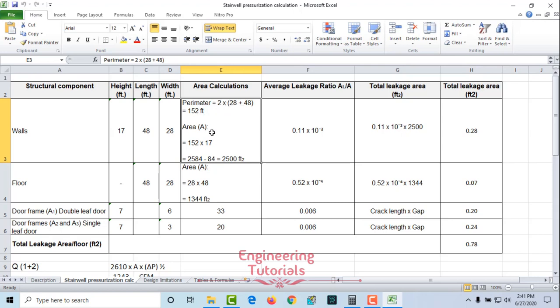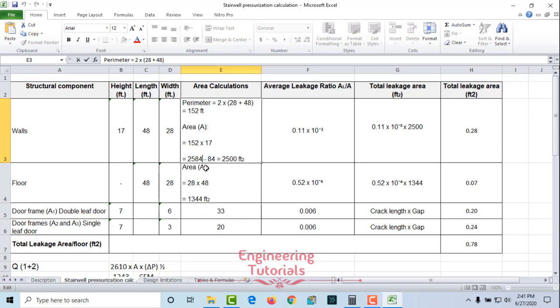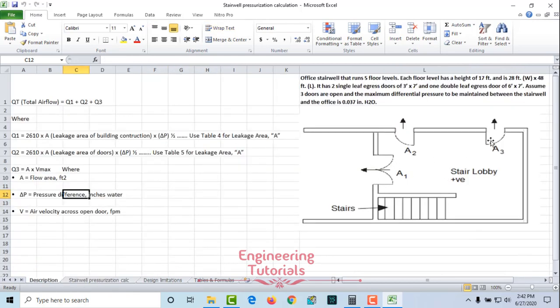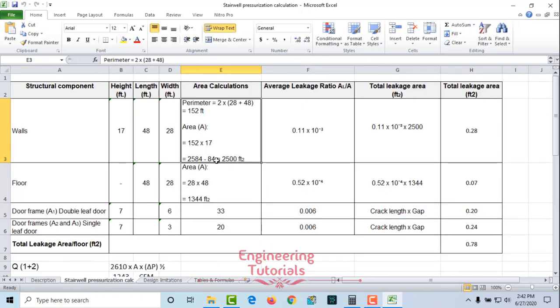First we calculate Q1 — the leakage through the building construction. The perimeter of the stairwell is 2 × (48 + 28) = 152 feet. With a floor height of 17 feet, the total wall area is 152 × 17 = 2,584 square feet. We subtract the door area: the double-leaf door is 6×7 = 42 sq ft, and the two single-leaf doors are each 3×7 = 21 sq ft, giving a total door area of 84 sq ft. So wall area = 2,584 − 84 = 2,500 square feet.